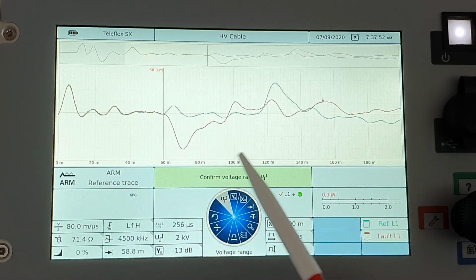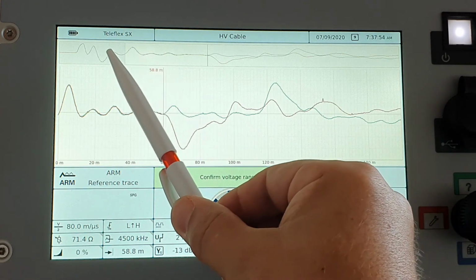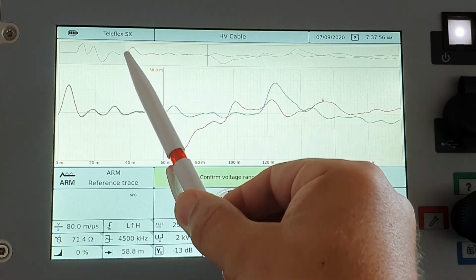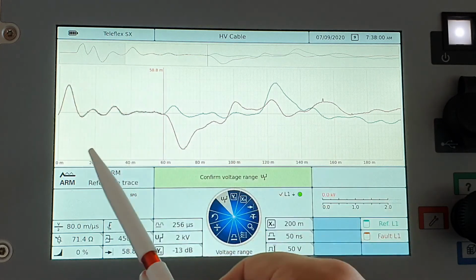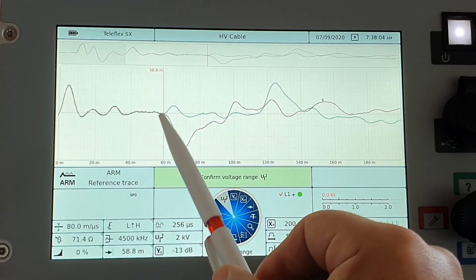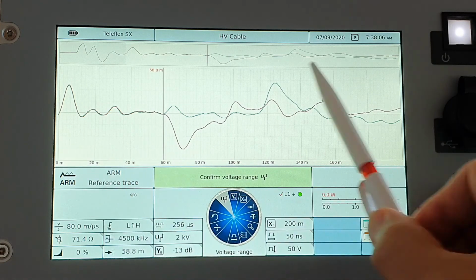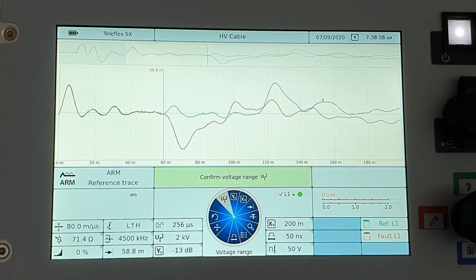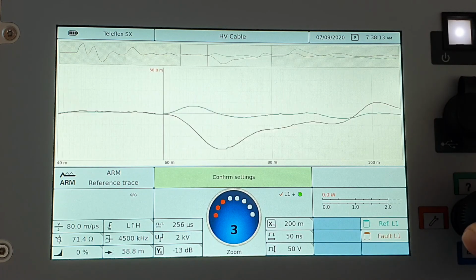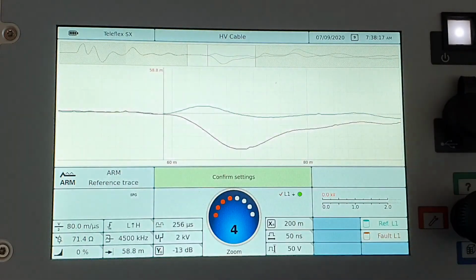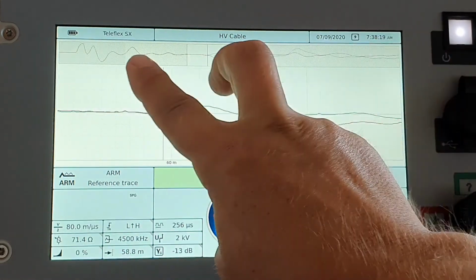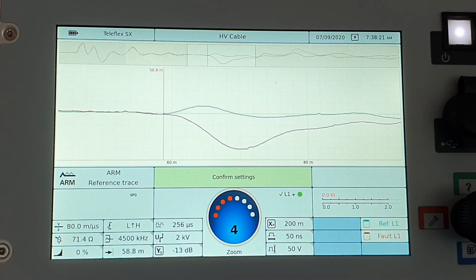I see my measurement. Up on the top window, I see my 0 start point. The rest is inside the van, so I don't need to see that. That's why on the big picture it's out of the image. And here I see my big measurement and I see it up here. If I click into the zoom, it will automatically zoom around my end cursor. And on the top window, I see where on my whole cable length am I, so I don't get lost.